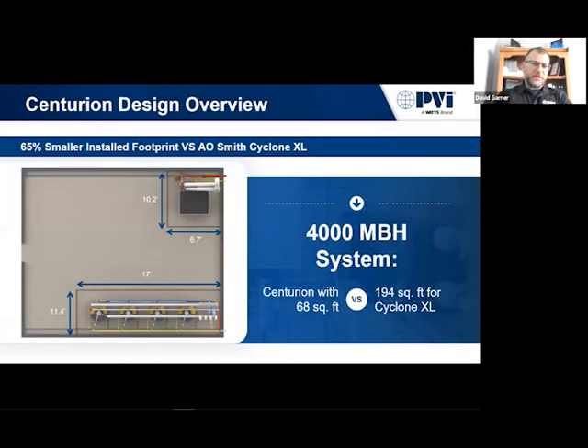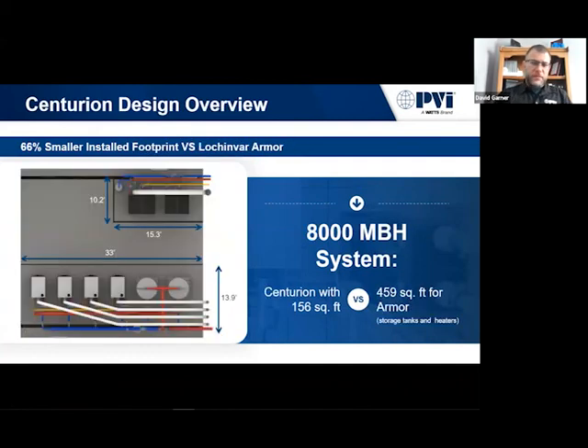The footprint itself is extremely small. These units can actually do zero clearance. We need to have 24 inches in between pairs of units to make sure we can perform all the PM service and be able to access any components for anything that could happen for maintenance in the future, repair, replacement. But it's going to drastically reduce the footprint for that water heating system you need in a building. For the venting, I'll just touch on that real quick, we can do common venting on these. We will need to go through and do a draft calc, but we have the ability to common vent without a draft system.